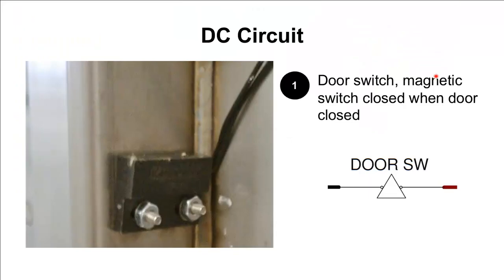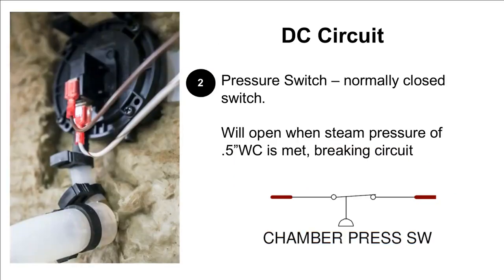The DC voltage first meets the door switch. It's a simple magnetic proximity switch. When the door is closed, the switch should be closed. And then we come to the pressure switch. This is the component responsible for controlling temperature in the unit. It is a normally closed switch. When we achieve steam pressure of 0.5 inches water column, it opens and breaks the circuit and stops the unit from heating. So if your unit is not heating, and you've confirmed the AC side is good, this is one of those that could be responsible.